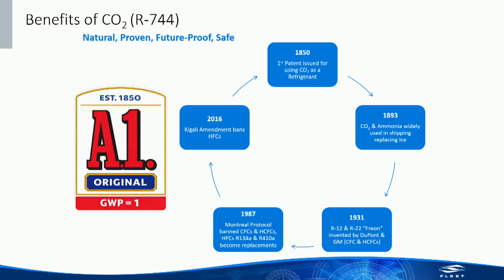Behind them came HFCs, R134A and R410A, something basically everybody here is probably very familiar with. Those had a pretty good run as well, about 30 years, until we started to understand the impacts they had on global warming. Then in 2016, a bunch of those same countries got together in Africa and decided that if we want to start using more heat pumps to electrify our countries, we don't want to be adversely affecting global warming, basically taking 2 steps forward and 1 step back by using these refrigerants. So those two have gotten banned, and you're starting to see that in place now, with 410A and 134 no longer being able to be manufactured and sold in New York State.